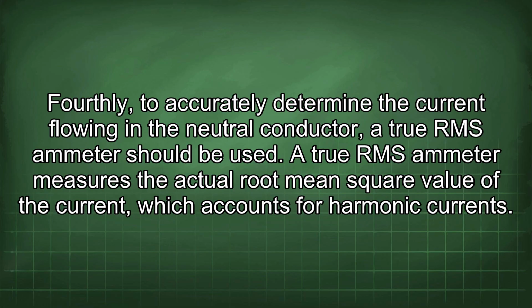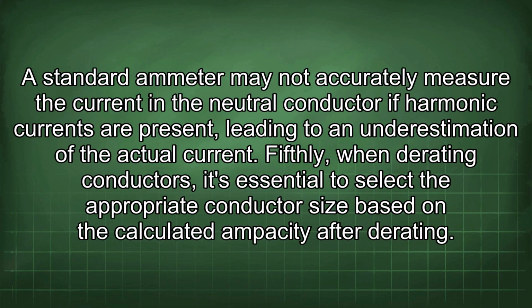Fourthly, to accurately determine the current flowing in the neutral conductor, a true RMS ammeter should be used. A true RMS ammeter measures the actual root mean square value of the current, which accounts for harmonic currents. A standard ammeter may not accurately measure the current in the neutral conductor if harmonic currents are present, leading to an underestimation of the actual current.